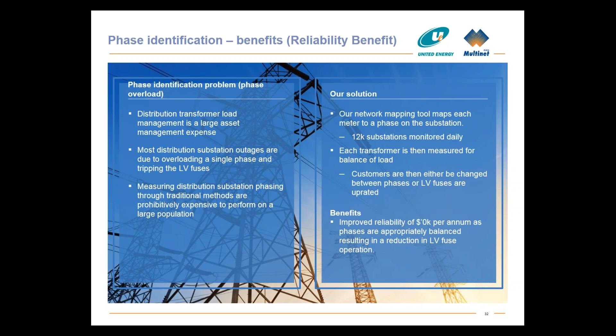What we also deal with is, a lot of times we want to do augmentation, and they just connect the customer to the closest phase. By looking at our loads, we can work out which customers are actually on what phase, and then for any new connections, make sure they go onto the correct phase - for example the blue phase - to balance connections out.